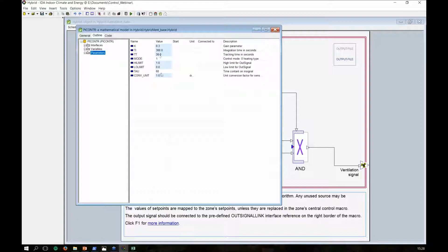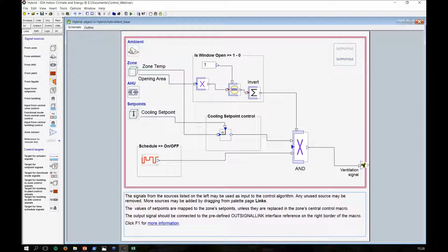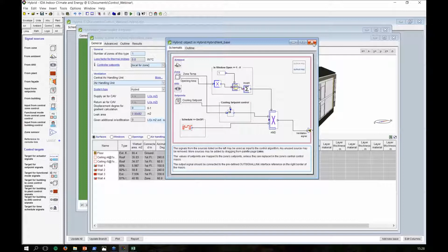I want mechanical ventilation. And for the mechanical ventilation here, I'm choosing to control this ventilation using temperature. So I'm taking my cooling set point to the PI controller, and then I'm measuring the zone temperature here. And I'm making sure that it stays at the cooling set point. Now, here you can use, of course, humidity, you can use pressure, you can use any type of control to send a signal to your ventilation. So in this combination between the mechanical ventilation and the natural ventilation, I'm able to avoid this overlapping system.